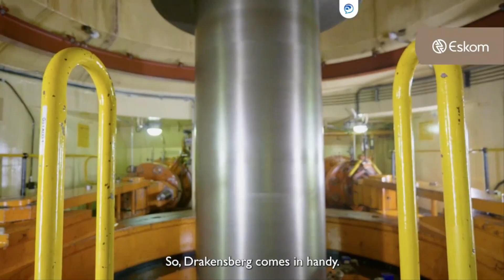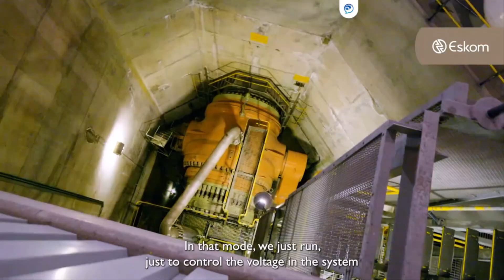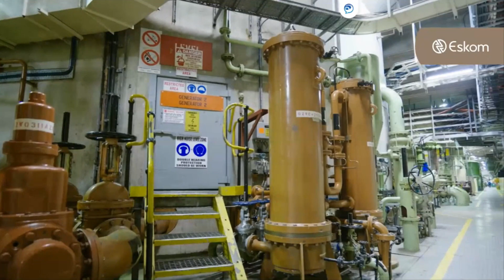Drakensberg is a pump storage scheme. Our operation is that we generate and we also pump, so during low demand we pump. We are also essential for controlling the voltage in the system, because our network is vast and there are a lot of differences in voltage, so Drakensberg comes in handy. We've got a mode called SCO, synchronous condenser operations, where we just run to control the voltage in the system and absorb the megavars.